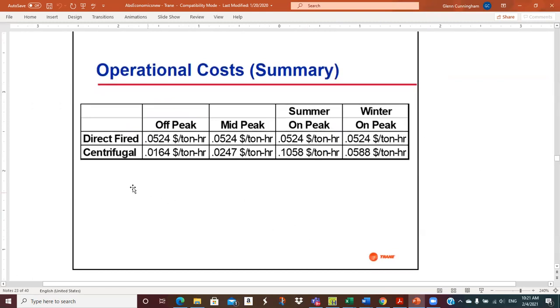So then for the direct fire, it's the same cost because that gas rate we're assuming doesn't change. So it's the same 5.24 cents per ton hour for on-peak, off-peak, mid-peak, whatever. It's the same throughout the year. Centrifugal, though, changes because the electric rates change. So if we run it off-peak, then that demand charge is much less. So we see off-peak centrifugal 1.64.